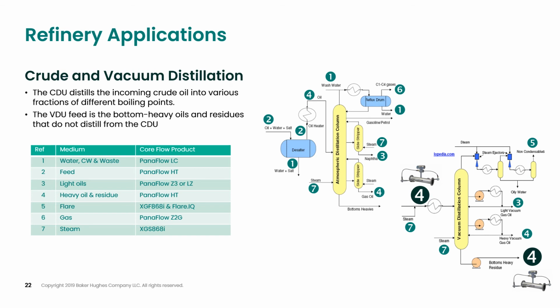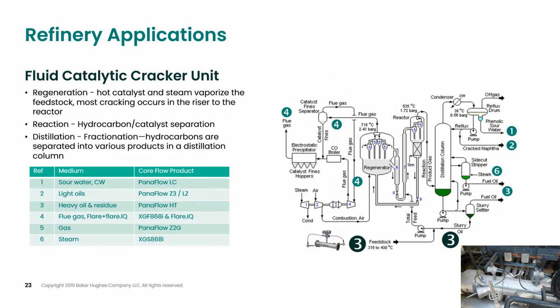Panaflow HT meters have been used especially for the crude distillation outlets or vacuum distillation inlets and at the vacuum distillation heavy bottom outlet. The fluid catalytic cracker unit is another process unit designed to crack or break the longer chain hydrocarbon fluids into more valuable products. Similar to the delayed coking unit and the main distillation units, we have a wide selection and variety of ultrasonic flow meters tailored for each measurement point. Panaflow HT meters have been used especially for the slurry oil and feedstock due to the high temperature and critical nature of these measurements. On the bottom here is a picture of one of these meters installed at the FCCU.